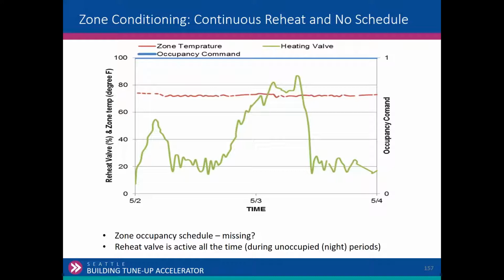So this is an example that PNNL provided. Essentially, the zone temperature up there, the heating valve is opening, and for zone occupancy schedule, there is no zone occupancy schedule. So essentially the reheat valve percentage and zone temperature, it's just sitting there heating. There's no schedule in there. The reheat valve is active all the time during unoccupied and night periods. So we don't want VAV boxes heating zones at 12 o'clock at midnight or during unoccupied periods. So we can look for those VAV boxes that we're going to do functional testing. We can look at valve position, status, zone temperatures. We can trend that and verify that they're being set back.